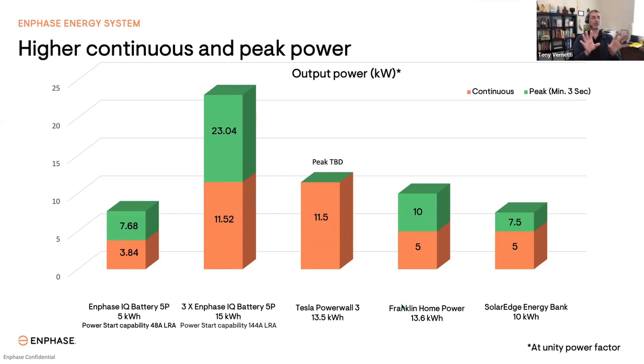The Powerwall 3, just to give you a sense of the comparison of power, has a very similar continuous power rating of 11.5 kilowatts compared to, again, the Enphase 3 of the 5Ps at 11.52. And the peak power rating is not stated on their spec sheet, but they do have locked rotor amps also mentioned on their spec sheet, which is very similar. I think it's about 148 locked rotor amps. So in terms of power and performance and starting capability, 3 of the 5Ps is very similar to the Powerwall 3. And then to the right, we've got the Franklin Home Power at 13.6 kilowatt hours, so about the same capacity, but its continuous and peak power is much, much lower.